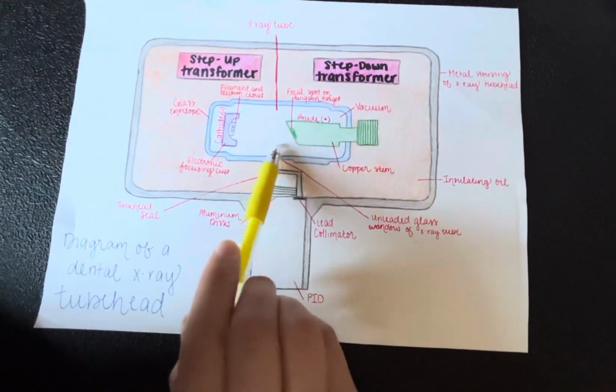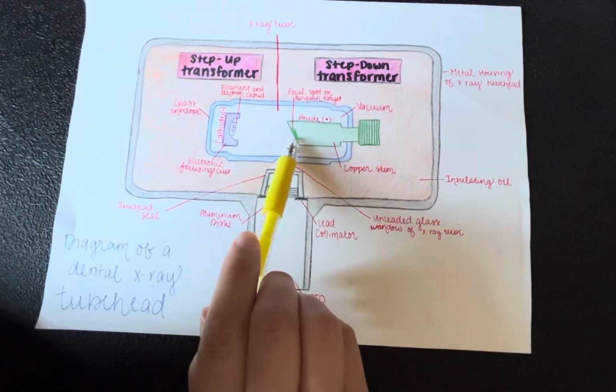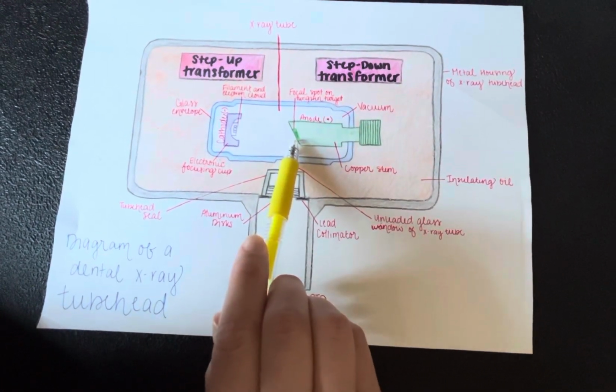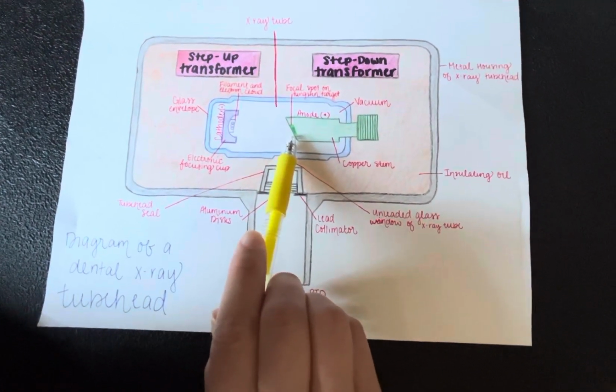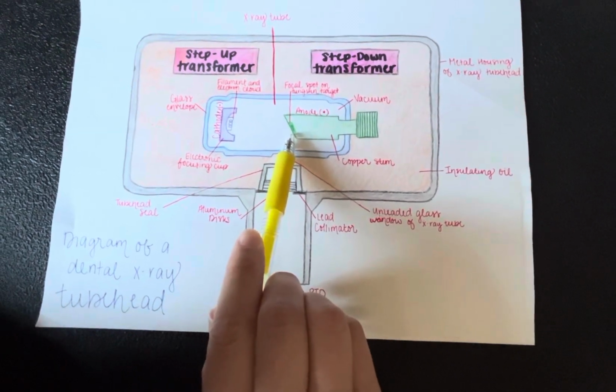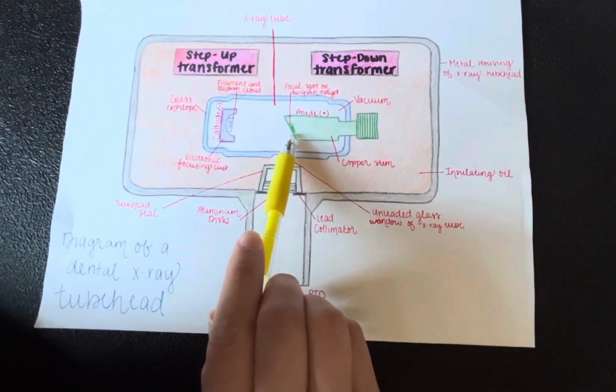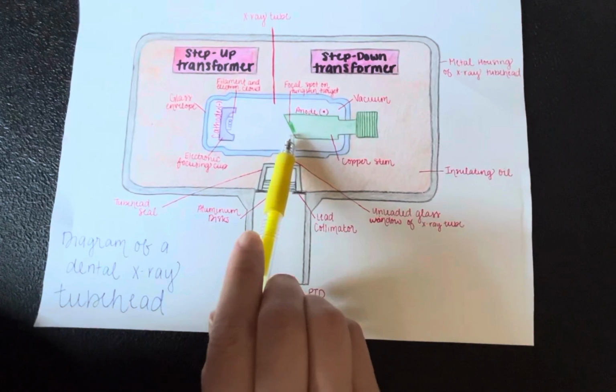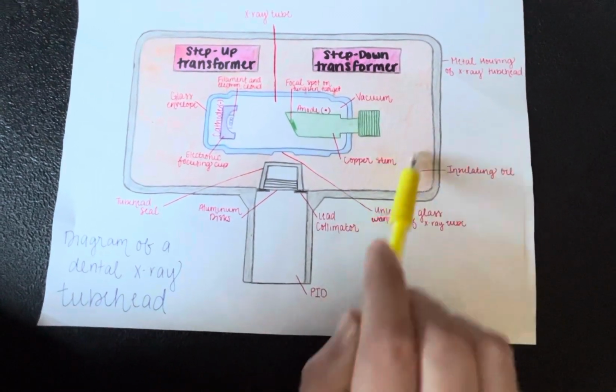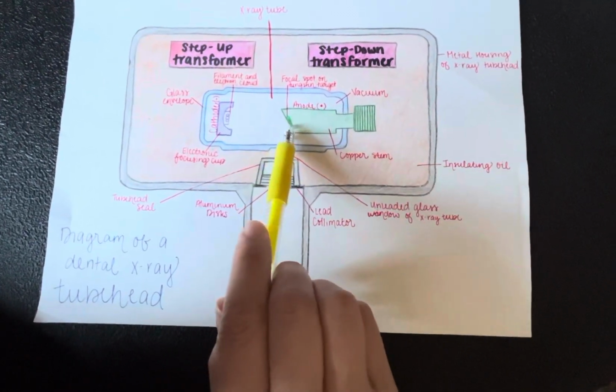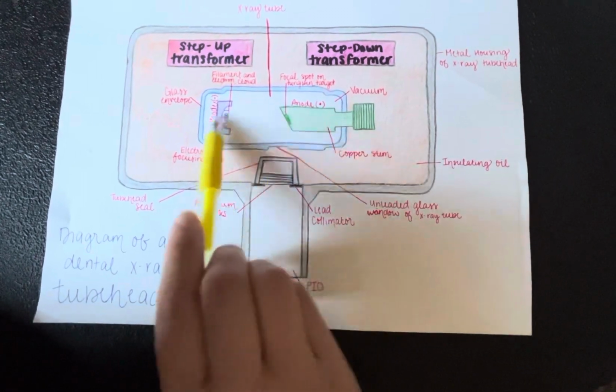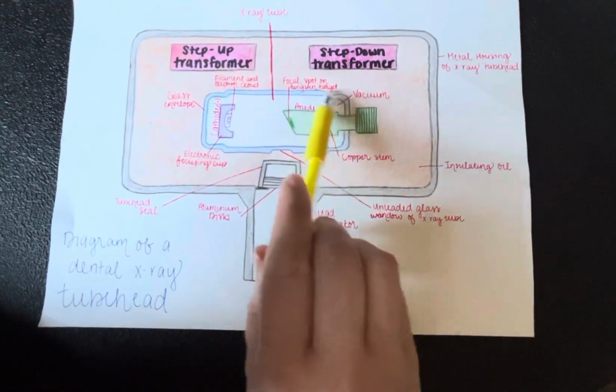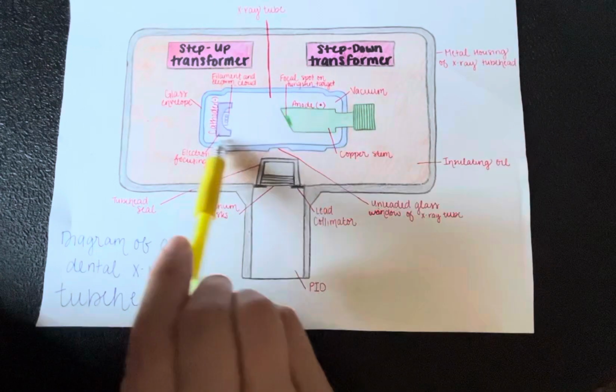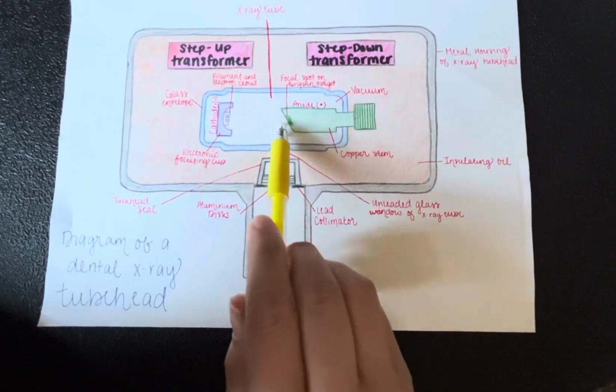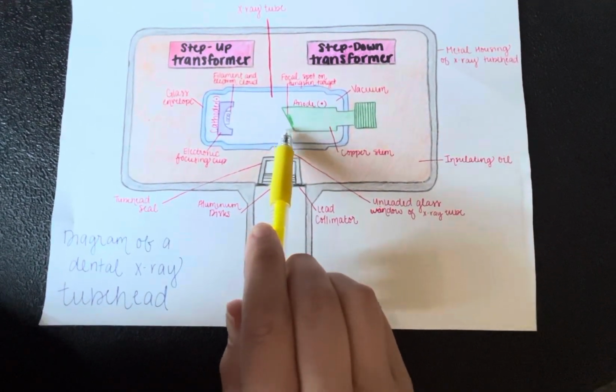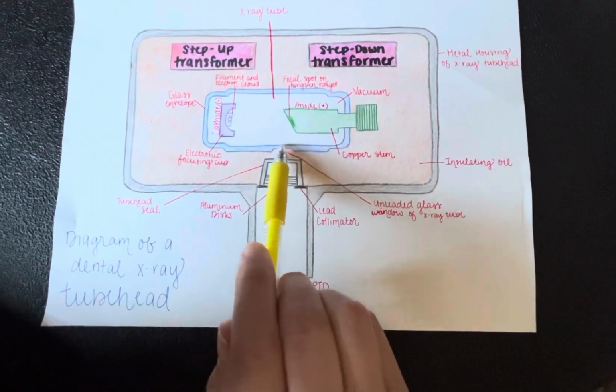When the electrons hit the tungsten target of the anode, the kinetic energy is converted to X-rays and heat. Less than 1% of the energy is converted to X-rays. The rest is converted to heat, which shows the need for the insulating oil to absorb the heat. The X-rays produced go in all different directions, but the glass envelope keeps them inside the tube. A small number of X-rays escape through the unleaded glass window.